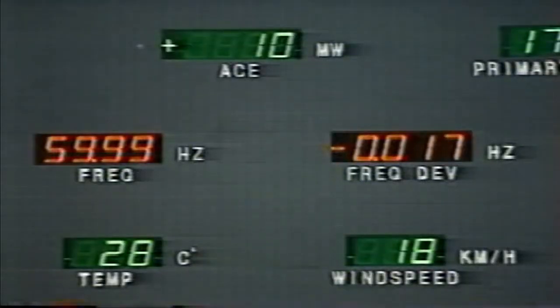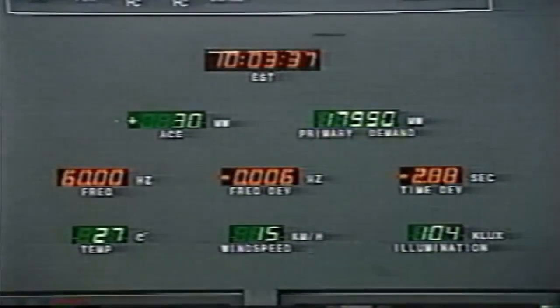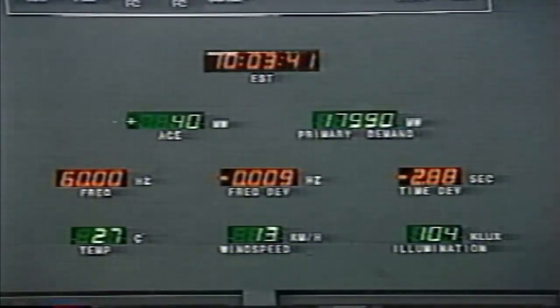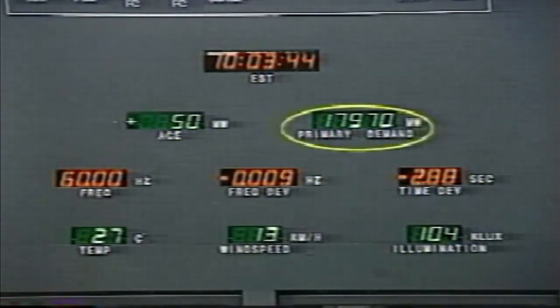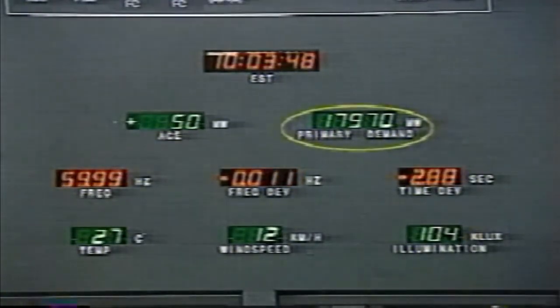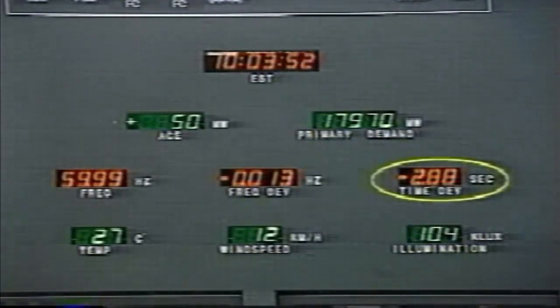The system frequency will be indicated on a wide range, say 55 to 65 hertz, as well as on an expanded scale over a smaller range, such as 59.5 to 60.5 hertz. The wide-range frequency scale might be necessary to record large frequency swings during very severe disturbances. One section of the control room will display information related to interchange with neighboring utilities. Often a large TV screen will provide up-to-date weather maps and forecasts. Other indications relate to the automatic generation control equipment, including area control error and primary demand, that is, load. In this control room, we also have the time deviation indicated.